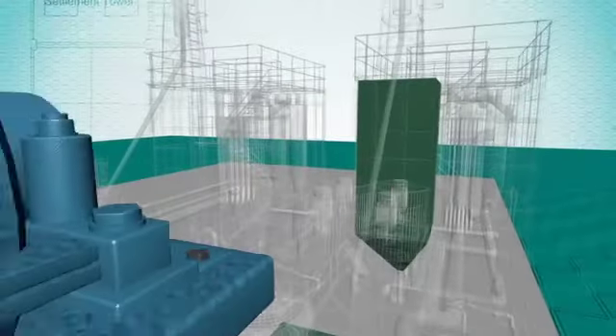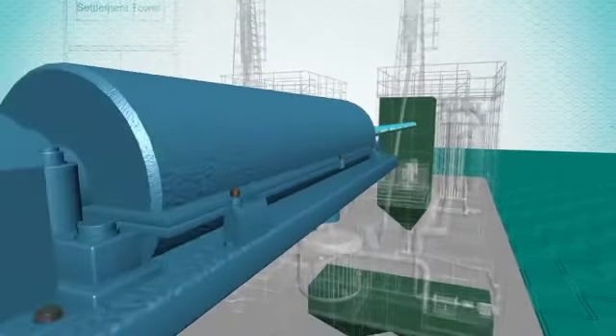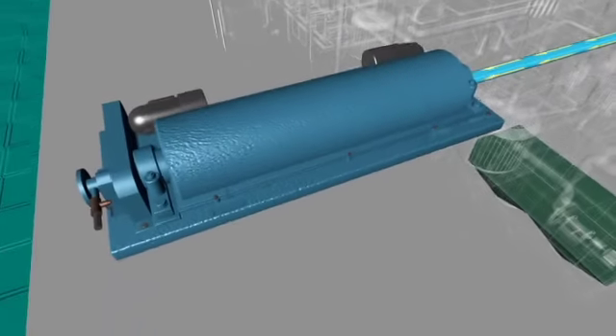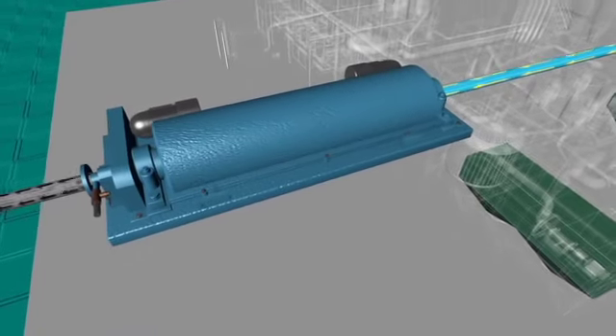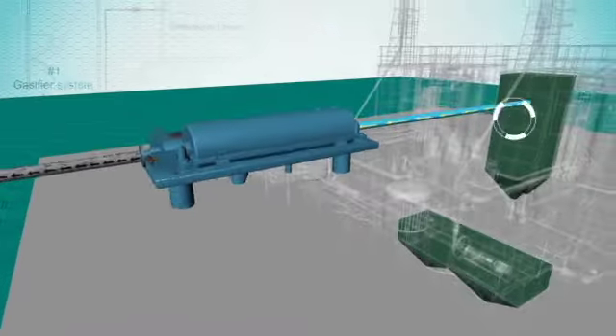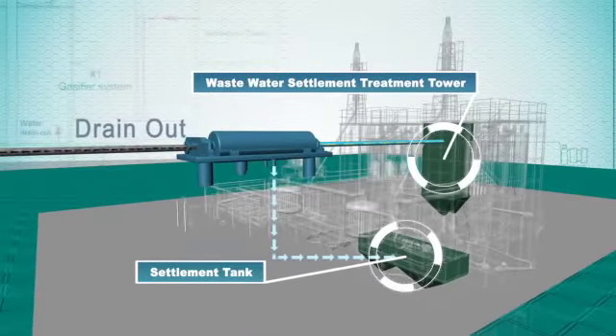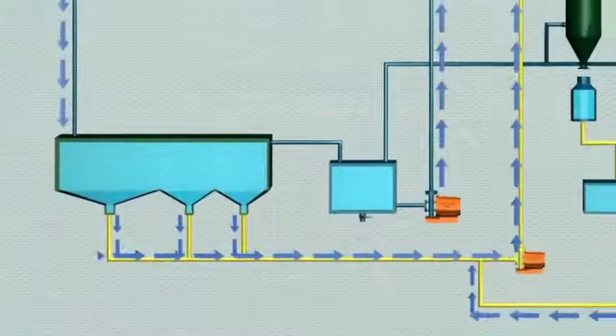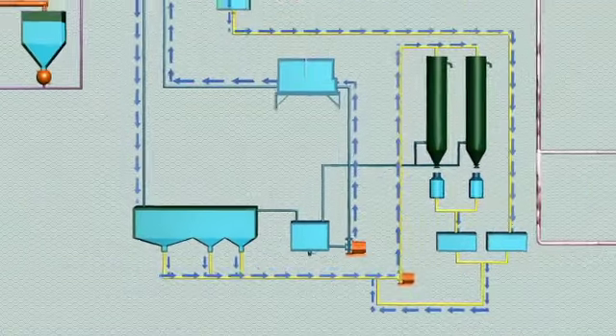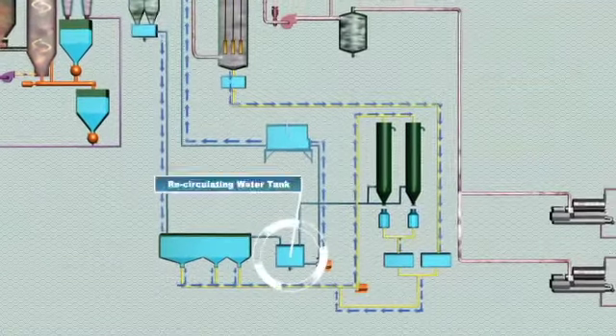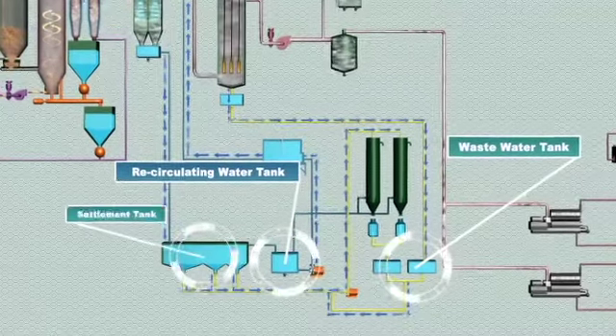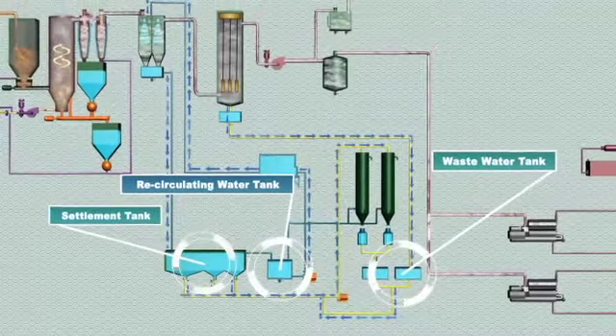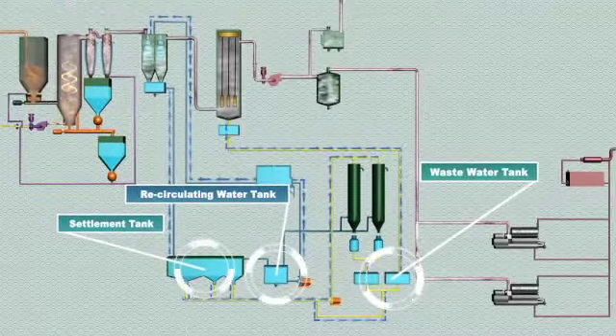The contaminated recirculating water passes through the settlement tank, where floating ash is pumped to the centrifuge to separate out solid from water and treated. The treated recirculating water is collected in the recirculating water tank to maintain a reasonable water suction level for the recirculating water.